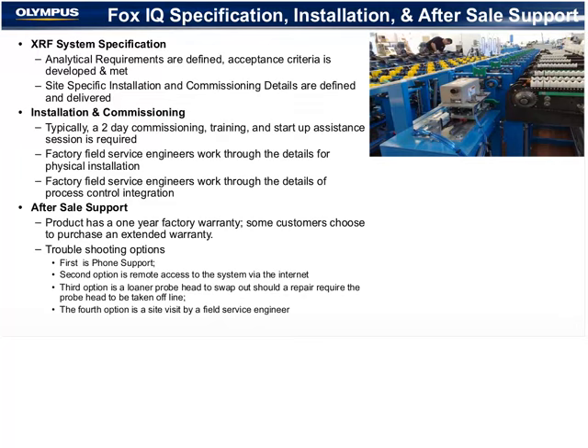Installation and commissioning, typically, as I've mentioned, a 2-day training and startup assistance is required. There's a charge for this. It's a few $1,000s, and it's more or less depending on how far it is from where our field service engineers are going to be embarking on their travel. The other thing that happens with the installation is the field service engineers work through the details of the installation and the process control integration.